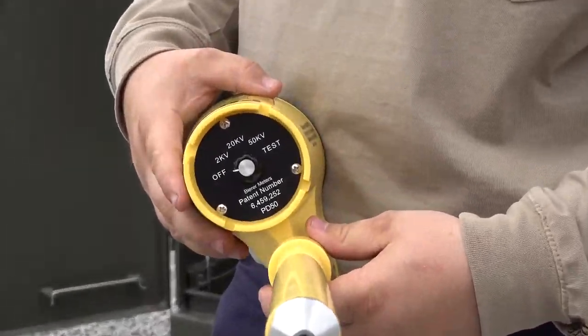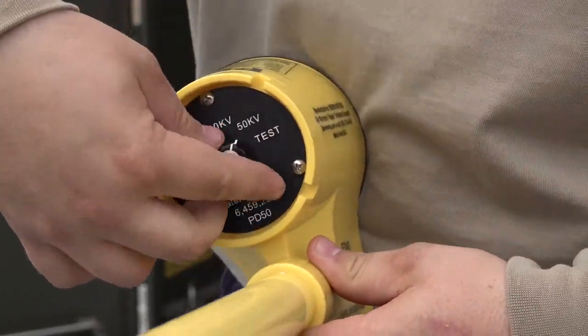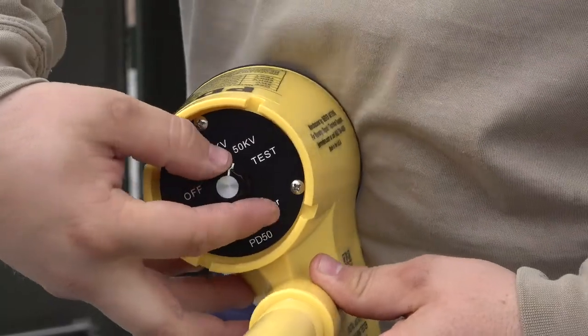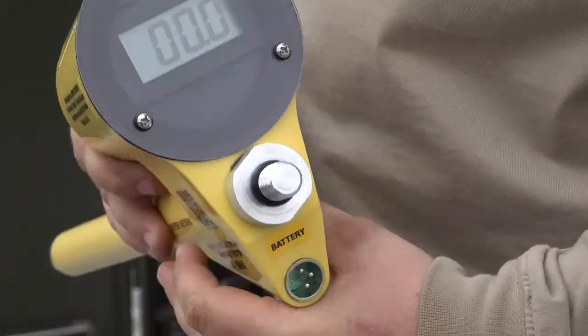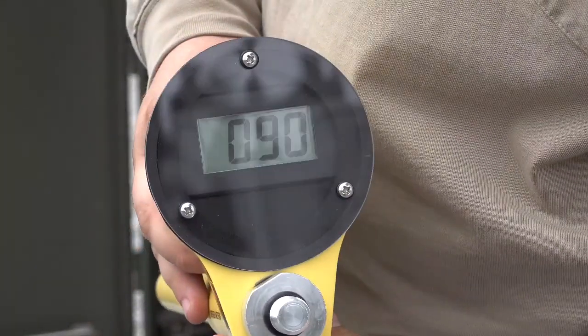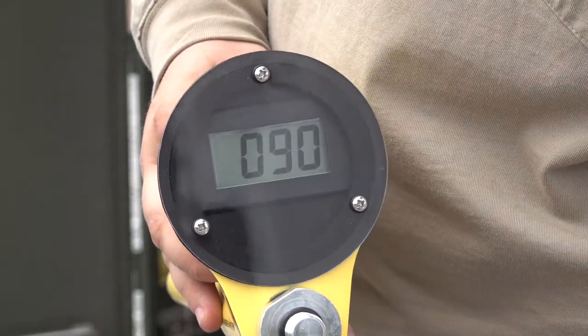Once all the visual inspections are complete, perform a self-test on the meter probe by turning the selector switch to the test switch position and hold it there for a couple seconds to determine the internal 9-volt DC battery voltage level. This meter displays a 90, so that means the internal battery has 9 volts. If the meter displays a 70, which is 7 volts or lower, it's time to replace the battery.